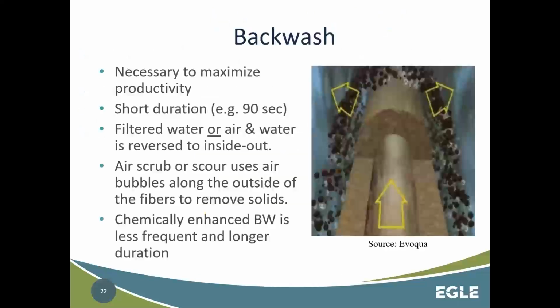All right. So backwashing. From previous presentations and perhaps from your operator experience, you're familiar with the backwashing of a conventional filter, but the backwashing of these is a little bit different. In this diagram here, it shows the backwash flow direction. Of course, during normal operation, we would have this outside in configuration. So these arrows would actually be reversed during normal filtering.